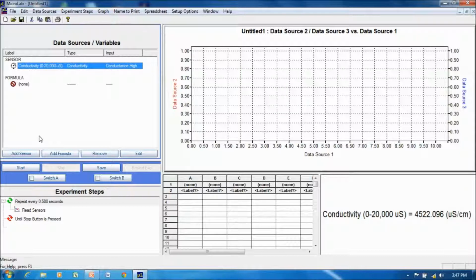So again, this is a second order fit over an extremely wide range from 0 to 4,500 microsiemens per centimeter. Actually, 3 orders of magnitude. Again, for the best results, it's recommended that you know what your range is going to be for your measurements and that you calibrate over that range. You get a much better fit and you get much better reproducibility. In the next video, I'll show you how to set up an experiment using the conductivity sensor. Thanks for watching.